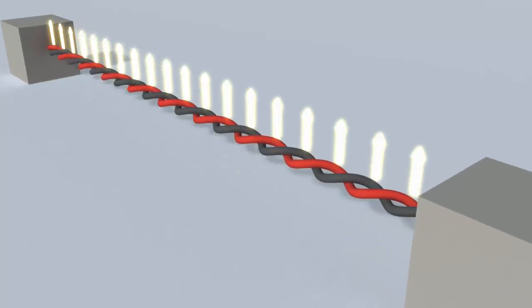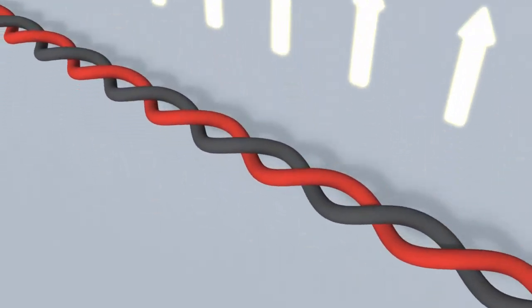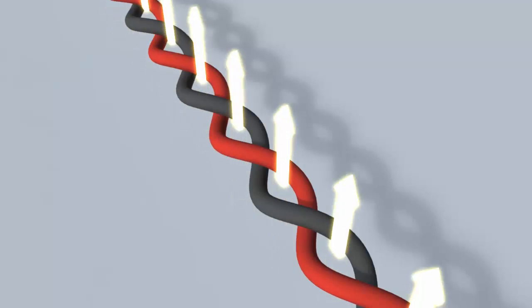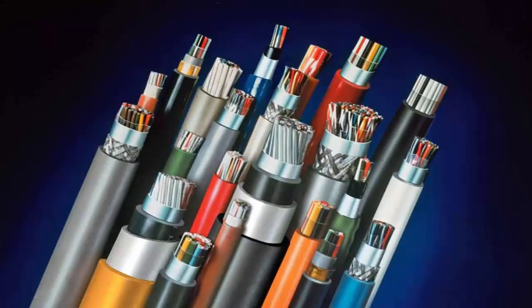By twisting back and forth, the noise current generated by external interference affects the signal levels in both wires in roughly the same way, effectively cancelling itself out and leaving the voltage difference on each line largely unaffected. This is what gives RS-485 its impressive range.